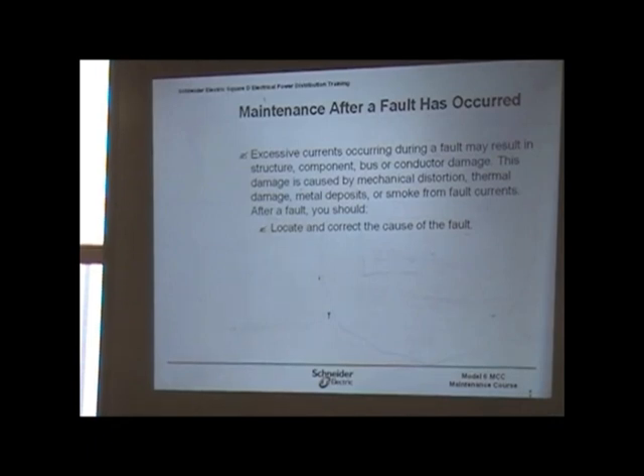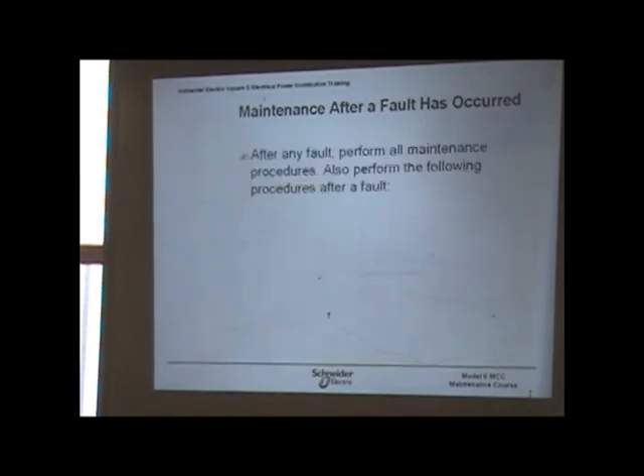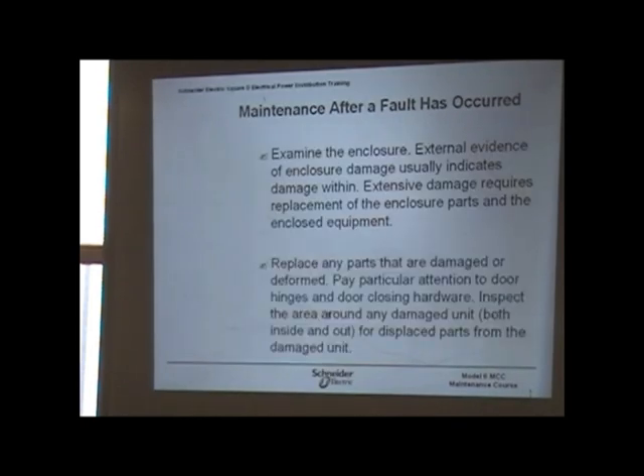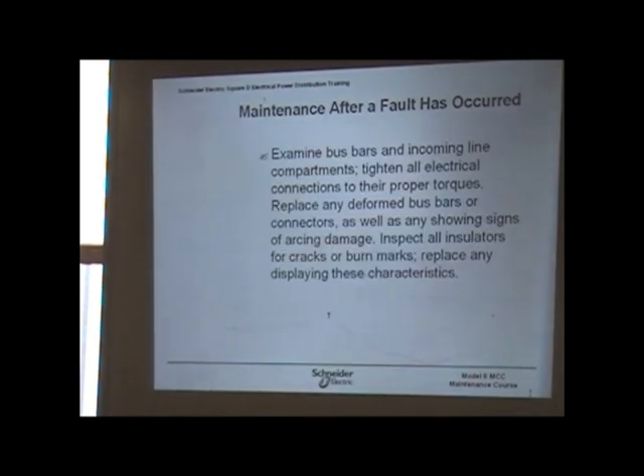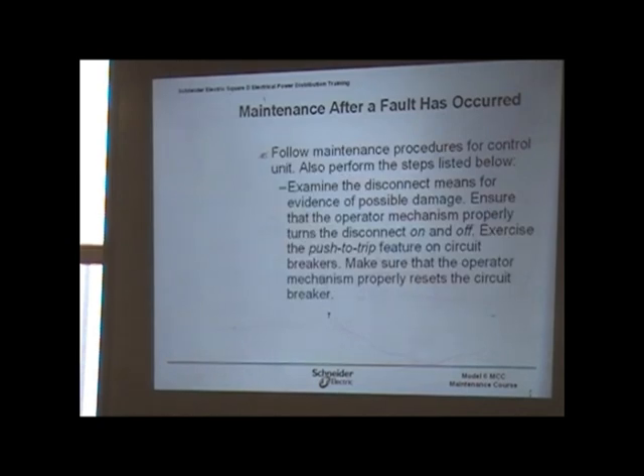Maintenance after a fault has occurred is the same as maintenance after water damage - the same process. You're going to examine the enclosure, everything, the bus bars, check everything, inspect for cracks, burn marks, and replace anything that has pitting or looks burnt.